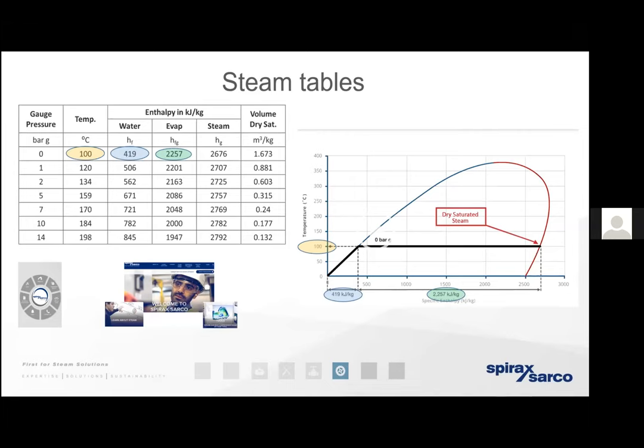What's left behind in the liquid condensate, which is the byproduct of heat exchange, is the enthalpy of water shown in the first column. For example, if we were condensing steam at atmospheric conditions — zero bar gauge, 100 degrees — the condensate would exist as a liquid at 100 degrees with 419 kilojoules of energy contained within it.